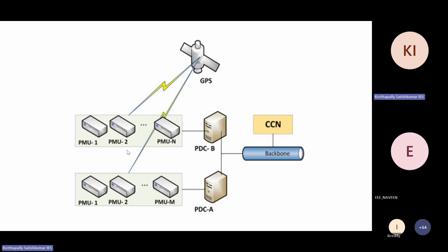As I mentioned, there are many PMUs in the power system, each synchronized with GPS, which acts as a reference. Once the PMU takes samples of data, its processor gives the output of phasors, and these phasors are transferred to the PDC. The PDC is nothing but servers located at the state load dispatch center, regional load dispatch center, and national load dispatch center.